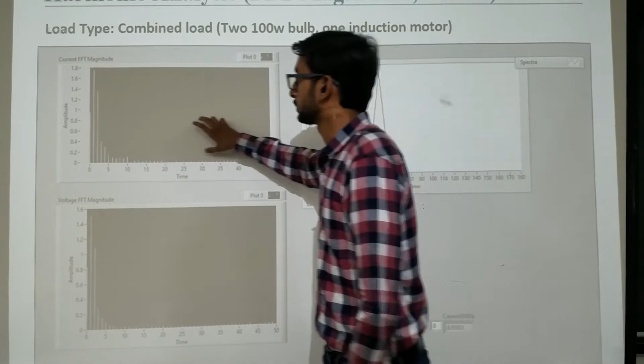As I already told, this is a waveform for the current FFT. As you can see, there is a magnitude change because of the load increase and the distortion between the current waveform and the voltage waveform. These depend upon the distortion, and as you can see there is a change in the components. There is a voltage THD in percentage and a current THD in percentage. This is for the comparison of our results with Fluke.